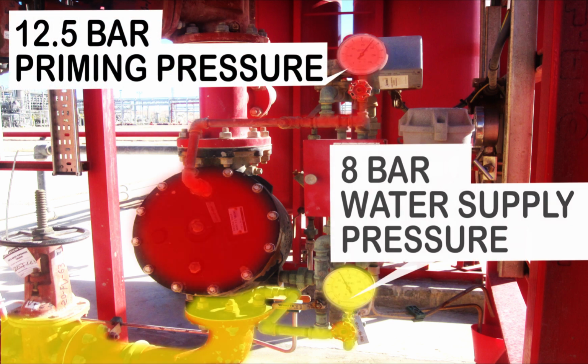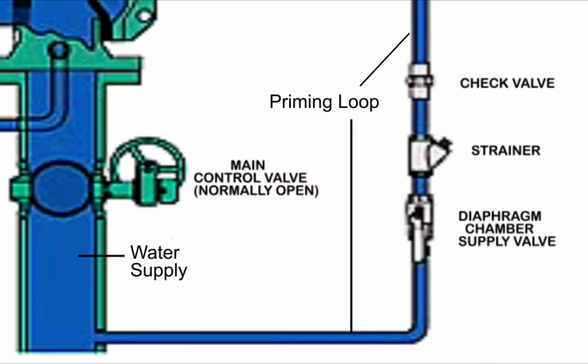However, the priming chamber here indicates a higher pressure, which is common to all the deluge skids present on site. This could be explained due to the presence of a check valve before the priming chamber. When the pressure of the fire water ring rises, the water supply pressure rises, causing the priming pressure to rise. When the pressure in the fire water ring falls again, the priming pressure remains high, due to the presence of the check valve which prevents the priming pressure from falling.